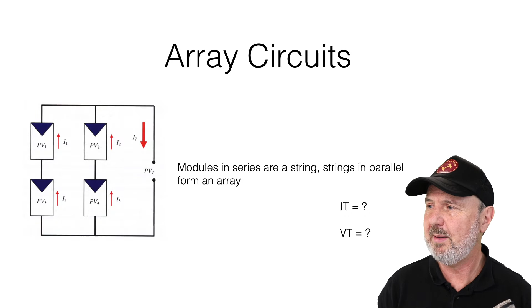So one of the issues that does happen with multiple panels connected together in combinations of parallel and series is when you get shading across single modules or a partial shading across an array. It doesn't take much to cause a solar panel to stop working in a string. And you might think that's surprising that putting your hand, literally your hand, across one cell on a panel will have a significant effect. It may even, if you put your arm across the short side of the panel, turn the whole panel off. And that's because they've got a safety feature. I've shown it here. It's called a bypass diode.